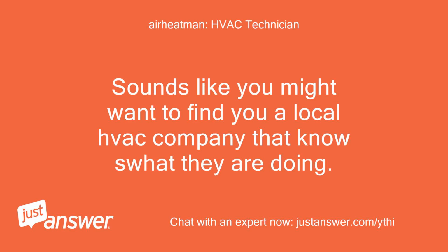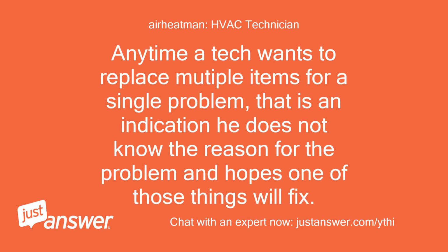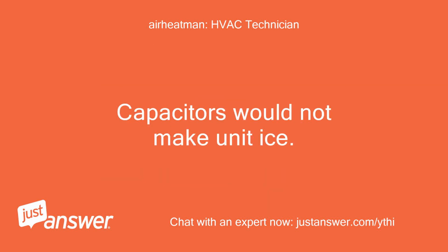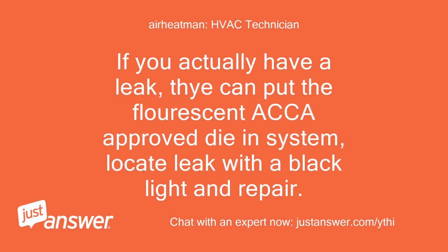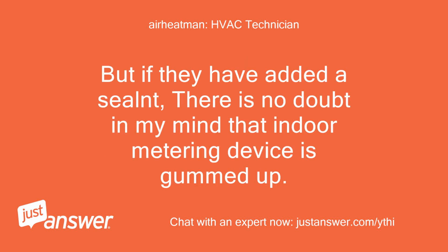Sounds like you might want to find you a local HVAC company that knows what they are doing. Anytime a tech wants to replace multiple items for a single problem, that is an indication he does not know the reason for the problem and hopes one of those things will fix. Capacitors would not make unit ice. If you actually have a leak, I can put the fluorescent ACCA approved dye in system, locate leak with a black light and repair. But if they have added a sealant, there is no doubt in my mind that indoor metering device is gummed up.